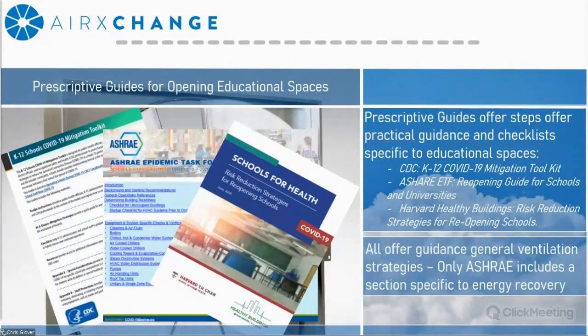All of them provide basic mechanical guidance, but really only the ASHRAE document has a section specific to energy recovery devices. So if your facility has an ERV, you're going to want to reference that document. Within that document, there is a reference to a document that I'm going to talk about shortly, which is the TC 5.5 practical guidance document.